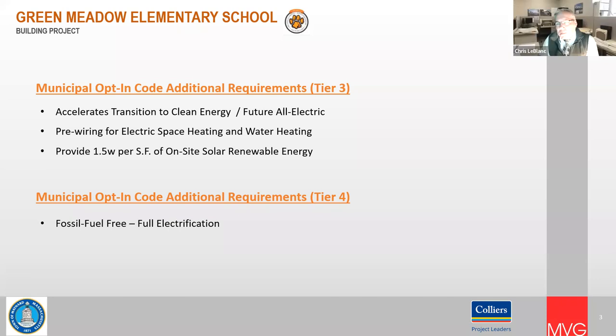Yeah, a quick question about tier three, about pre-wiring. As far as I recall, Eversource can't pre-wire a larger service for you. The service has to be for your anticipated load at the time they start it. So even if we did this pre-wiring, that's just our stuff in the building. And if we changed to a more electrified system for tier three or future tier four, they would still have to do quite a bit of work to bring in a new transformer, new service to the building, maybe some switchgear of our own would have to change if more power is coming through it. So it's not like a super easy swap. That's how I'm understanding it.